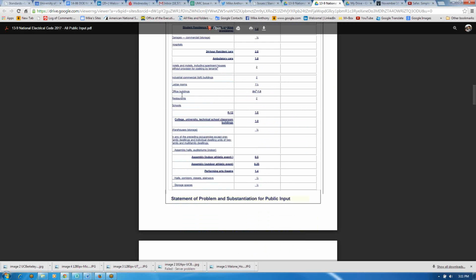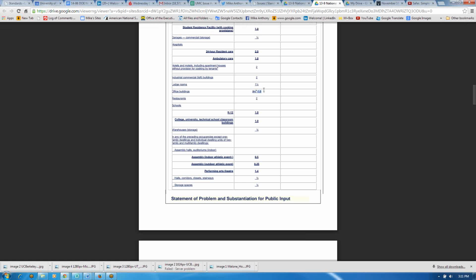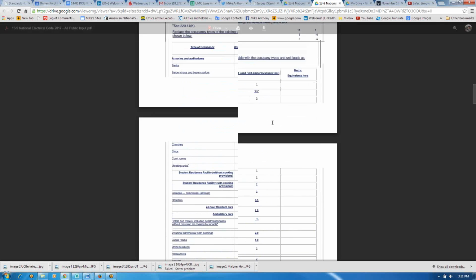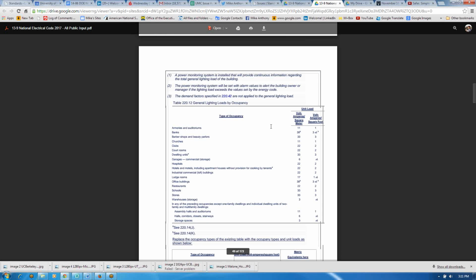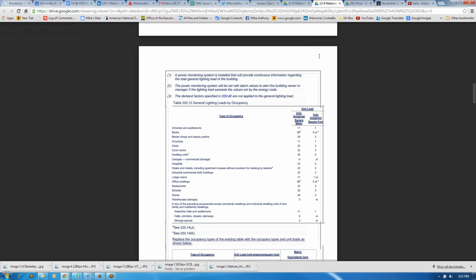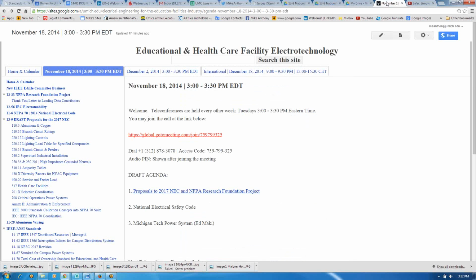We took the IBC occupancy types and the unit load volt-amperes from ASHRAE 90.1 and installed them here. For example, take this one, most meaningful to us: ASHRAE says we're limited to 1.0 watts per square foot, but he was asking us to design at 3.5 watts. As you know, we got an exception on that, but this is an example of what we tried to do to get clarity, because some designers are struggling with it. I hope that helps.